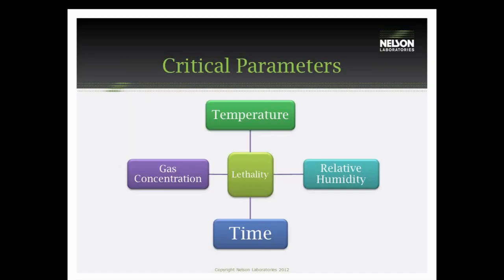There are four critical parameters for EO sterilization that contribute to the lethality of the process. Those are temperature, relative humidity, time, and gas concentration. We'll go over each one of these and talk about how they affect the sterilization.